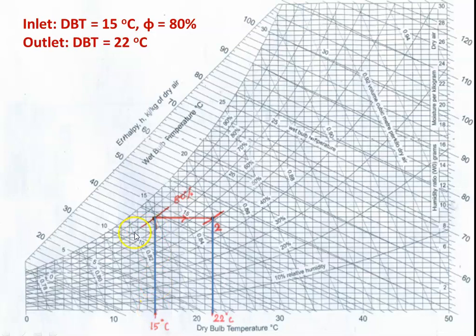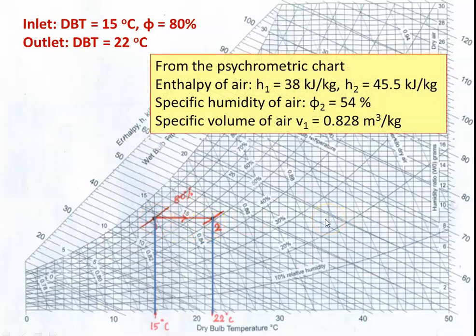From the psychrometric chart, read the required values. Enthalpy H1 = 38 kJ/kg, H2 = 45.5 kJ/kg. The relative humidity of the air at the outlet is 54%. The specific volume of air at inlet point 1 is 0.828 m³/kg. These are the properties we take from the psychrometric chart for our calculations.